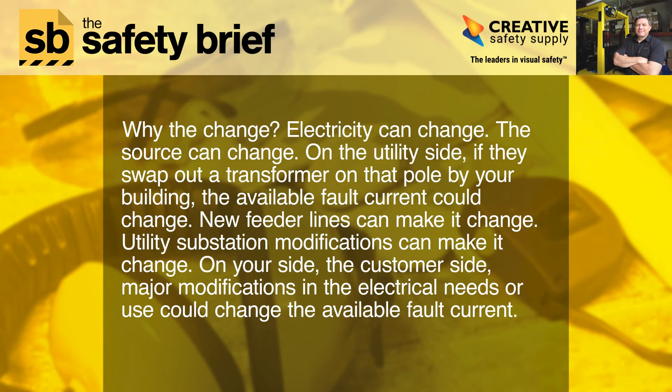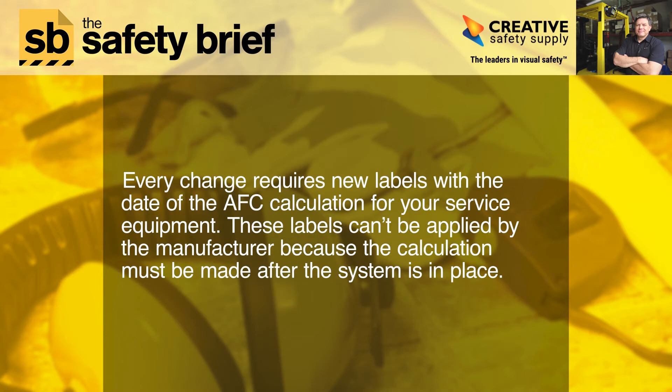Why the change? Electricity can change — the source can change. On the utility side, if they swap out a transformer on that pole by your building, the available fault current could change. New feeder lines can make it change. Utility substation modifications can make it change. On your side, the customer's side, major modifications in electrical needs or use could also change the available fault current.